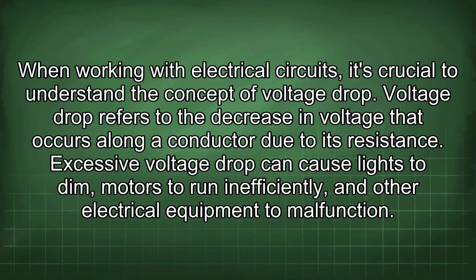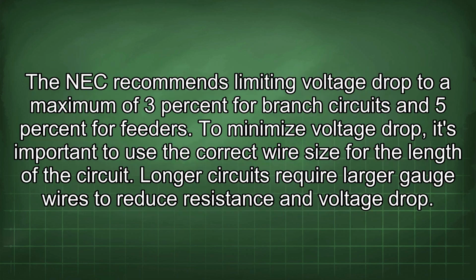When working with electrical circuits, it's crucial to understand the concept of voltage drop. Voltage drop refers to the decrease in voltage that occurs along a conductor due to its resistance. Excessive voltage drop can cause lights to dim, motors to run inefficiently, and other electrical equipment to malfunction. The NEC recommends limiting voltage drop to a maximum of 3% for branch circuits and 5% for feeders.